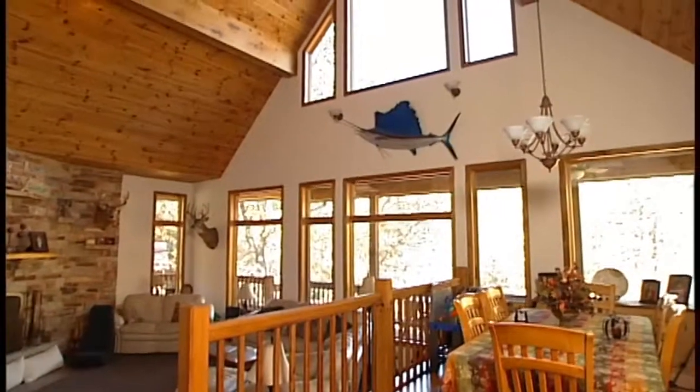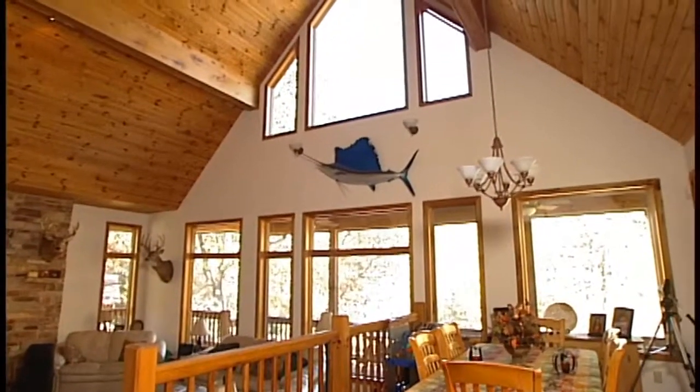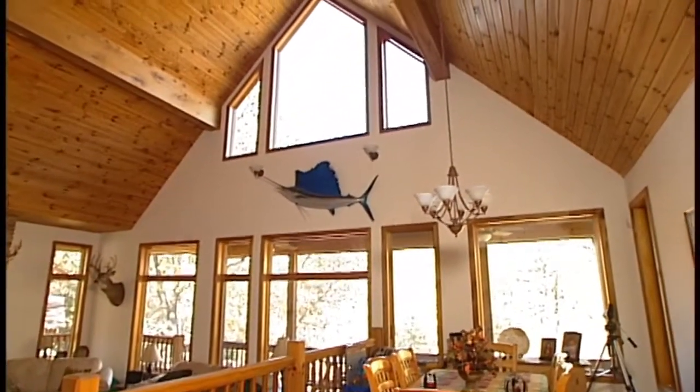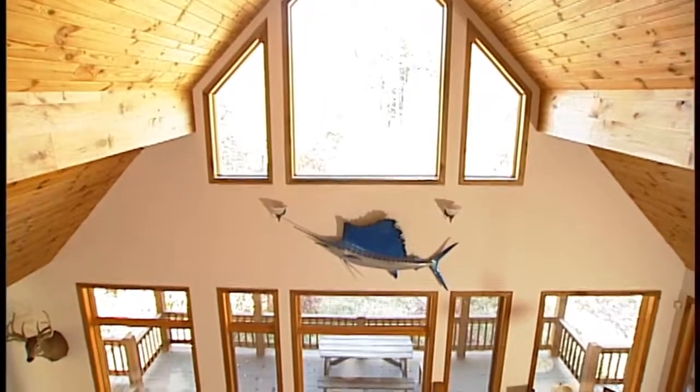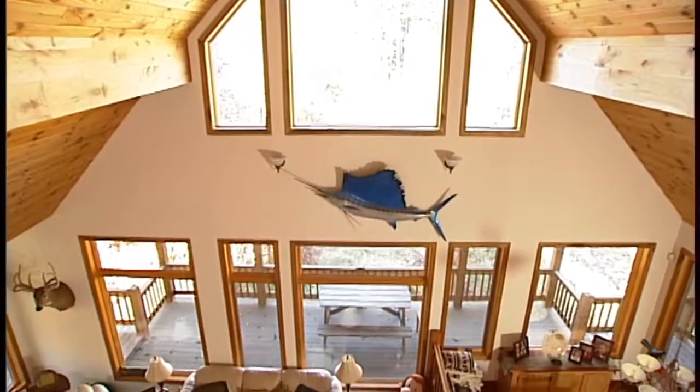And when the contractor is on site, what specifically are you looking for? Do you take a wall of windows like this? Does this create any challenges? Sure, this wall of windows is going to create a huge challenge, and that's the important thing. What direction does it face? How much sun is going to be shining in? In this particular case, from what you described, this faces east. So it's really going to be a morning load, and then from there it'll be fine the rest of the day.